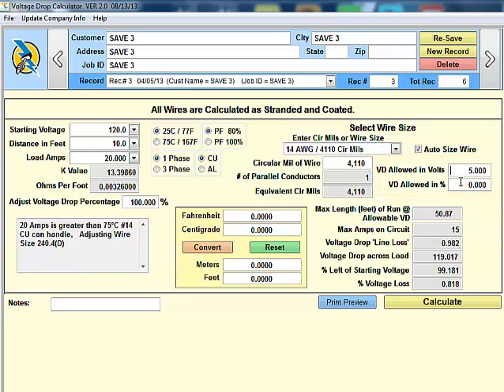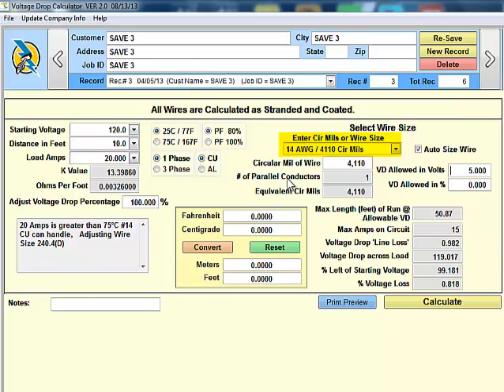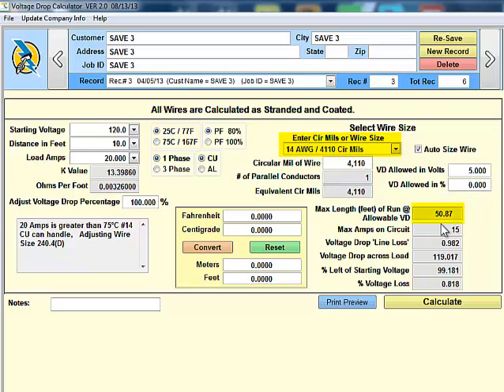At this point, we've chose that we want to have a maximum of 5 volts drop. We can see that the maximum length in feet at the allowable voltage drop is 50.87 feet. So using a 14 gauge wire, the maximum distance we can go to maintain this voltage drop is 50 feet.